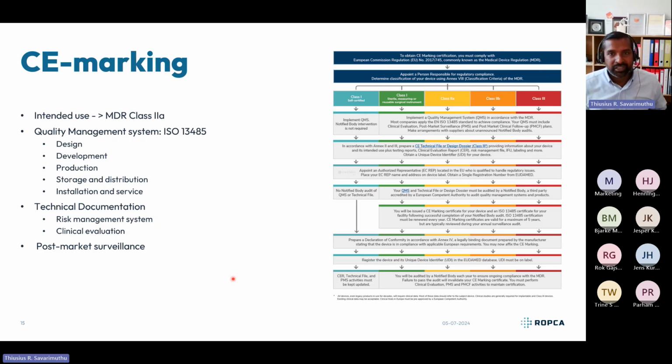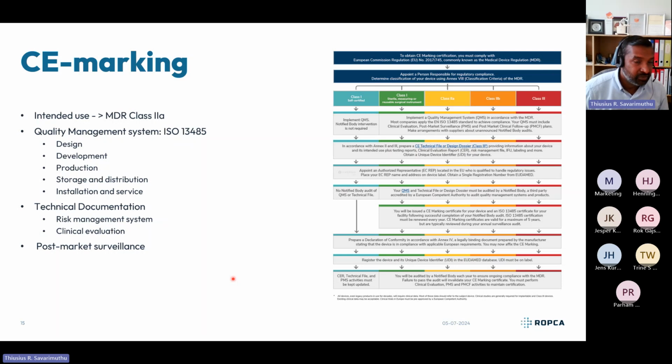In our case, it was a CE mark MDR class 2A, mainly dictated by the ultrasound machine interface we had. And based on that, we had to have a quality management system that needs to be supervised by a notified body. So we implemented that. And in that process, we also had to define and get used to a lot of processes.